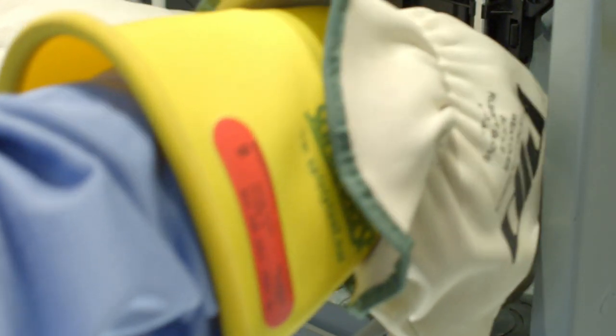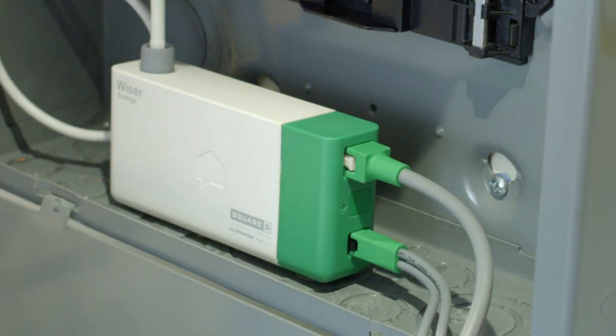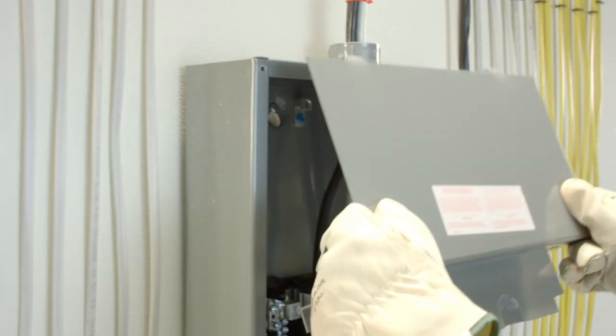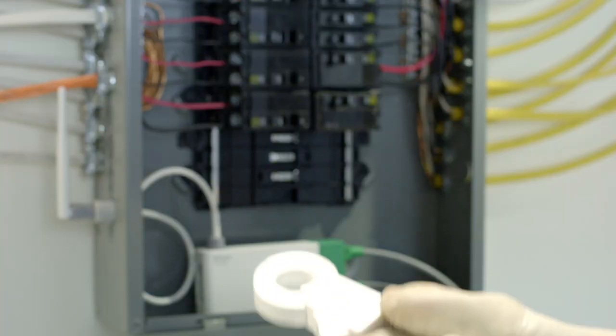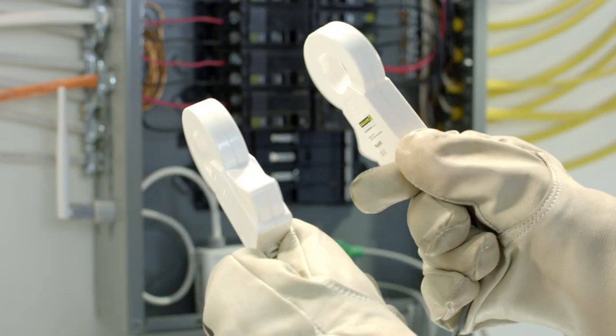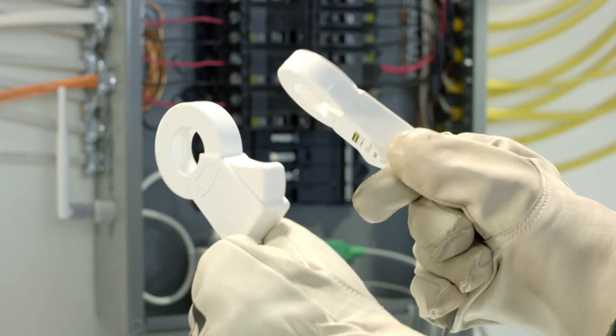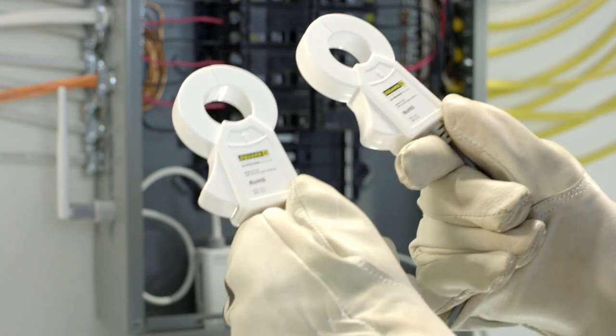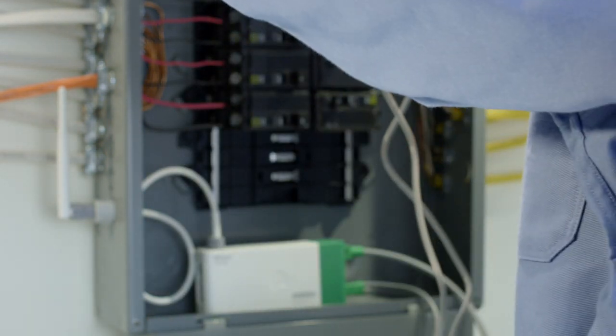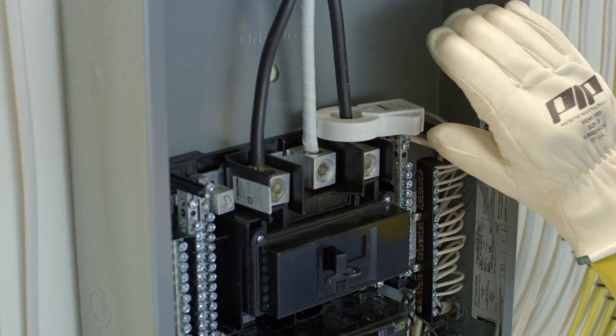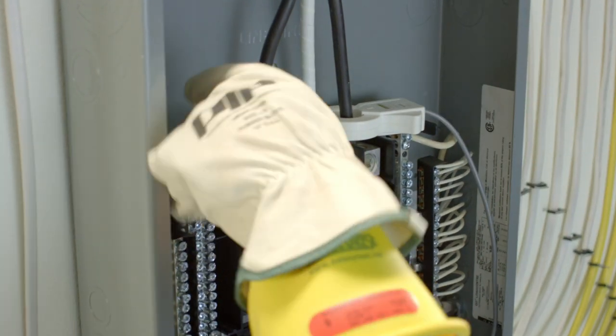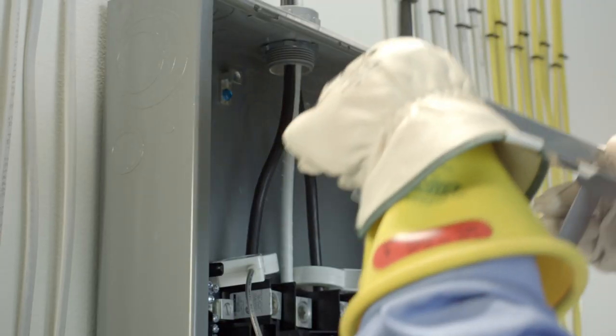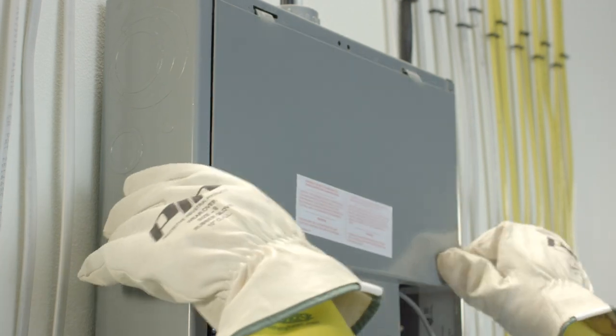Before attaching the current sensors around the main service cables, be sure you have plugged the sensor cables into the monitor first. After removing the main breaker barrier, clamp the current sensors around the two main service cables, ensuring the product labels on each sensor are both facing the same direction. They need to remain securely closed around the main service cables. Then reattach the main breaker barrier.